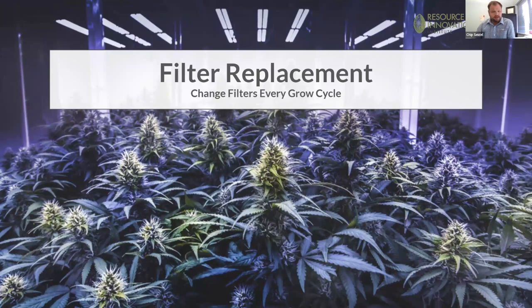Filter replacement is a really big issue. Most folks don't change their filters as frequently as they should, and it can have a very large impact. When filters get clogged, it messes with the static pressure within the units. The units draw additional amps trying to push air through the dirty filter, and you're not getting optimal results. It's a cheap insurance policy to change those filters and keep them clean, and it does wonders for your facility.